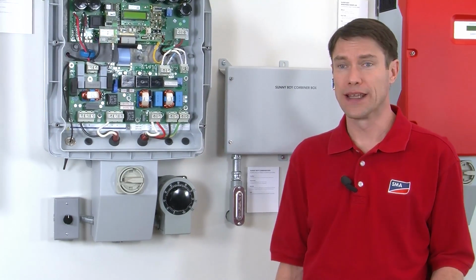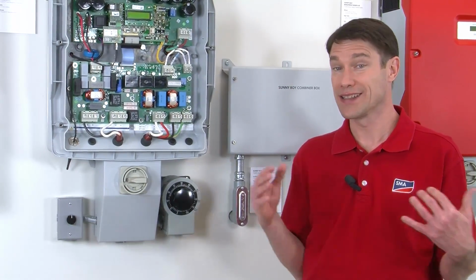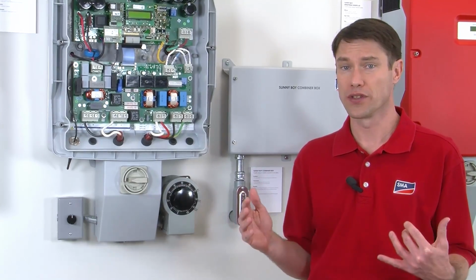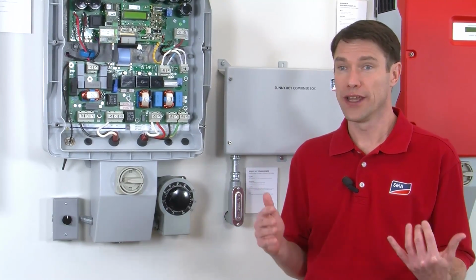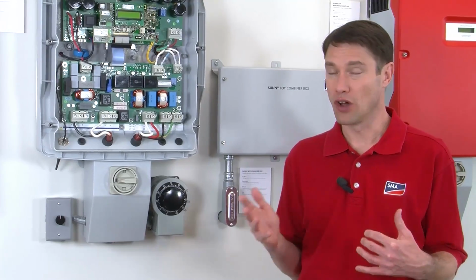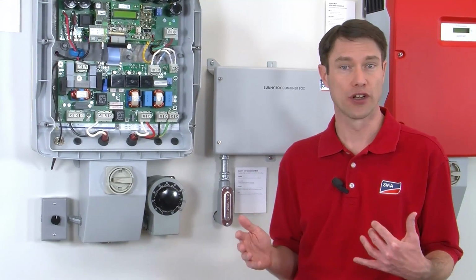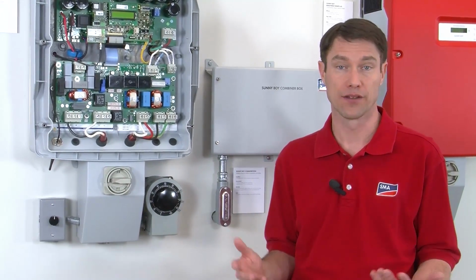If the inverter is seeing a non-zero frequency, but it's still outside of spec for the utility, then there's an issue. Then you really need to call the utility because that's something they should control and it's outside of your hands. So while FAC is a very common error, it should also be one that's very easy to remedy.